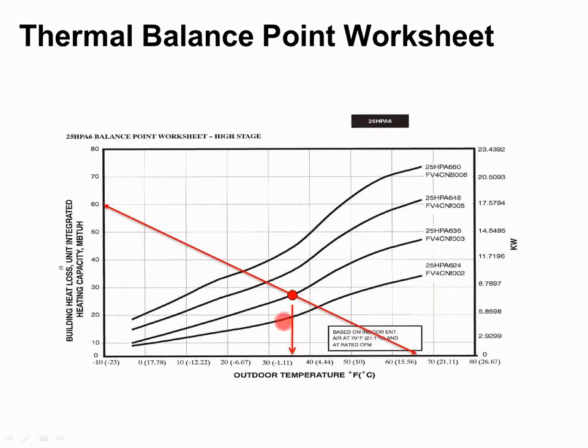The red line on a diagonal here, that's the load of my building, right? So when it is minus 10 out, this guy is a 60,000 BTU heating load. When it's 0 out, this guy's a 54,000 BTU load. When it's 50 out, he's an 18,000 BTU load, right? So I can graph that on the same graph as the outputs of those heat pumps are graphed on, and then I can pick which heat pump I want to see where the intersecting line is.